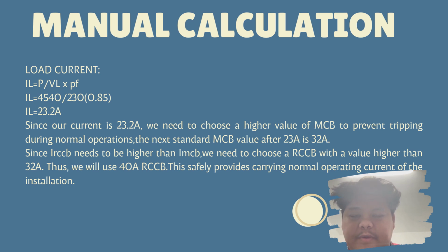VL and PF are already given in the question. So to calculate IL, it is 4,540 divided by 230 times 0.85, which gives 23.2 amperes. For the IMCB, since our current is 23.2 amperes, we need a value higher than 23 amperes. The next standard MCB value after 23 amperes is 32 amperes.